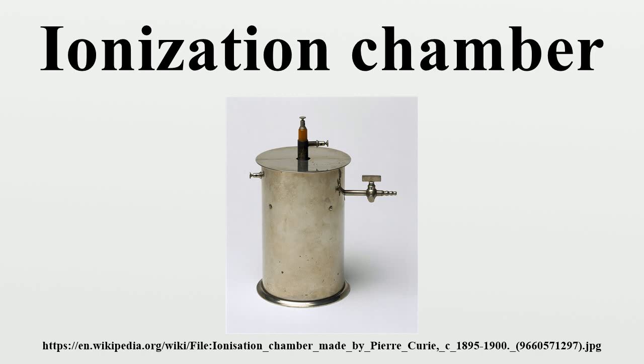Nuclear industry: Ionization chambers are widely used in the nuclear industry as they provide an output that is proportional to radiation dose. They find wide use in situations where a constant high dose rate is being measured, as they have a greater operating lifetime than standard Geiger-Müller tubes, which suffer from gas breakdown and are generally limited to a life of about 10^11 count events. Additionally, the Geiger-Müller tube cannot operate above about 10^4 counts per second due to dead time effects, whereas there is no similar limitation on the ion chamber.